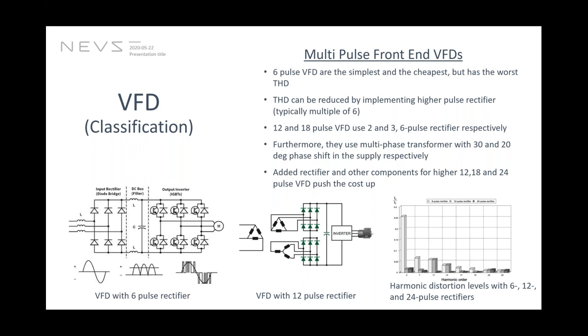Now the harmonic distortion of these multi-pulse VFDs can be improved by adding on more of these pulse rectifiers, as you can see in the middle picture in this slide. But if you are adding multiple 6-pulse rectifiers, then you need to phase shift accordingly. So basically, if you have 12 pulse or 18 pulse, you have 2 or 3 of the 6-pulse VFDs, and then you have to shift it by 30 degree and 20 degree phase shift respectively. The last figure that I have presented in this slide is a comparison of the harmonic distortion when you have 6, 12, and 24 pulse rectifier. It's quite evident that increasing the number of pulses will improve the total harmonic distortion.